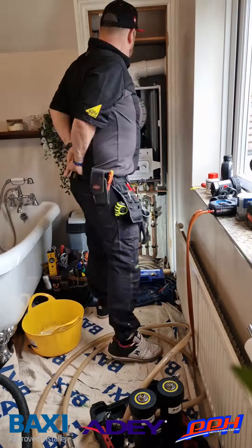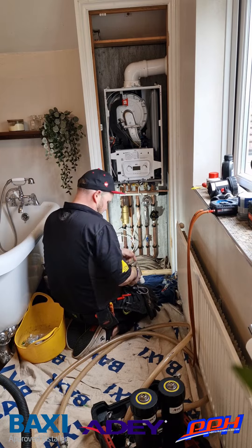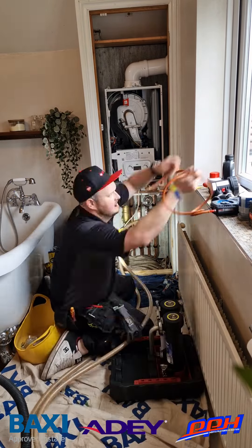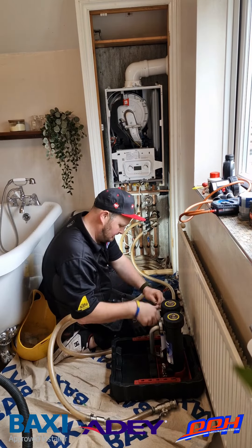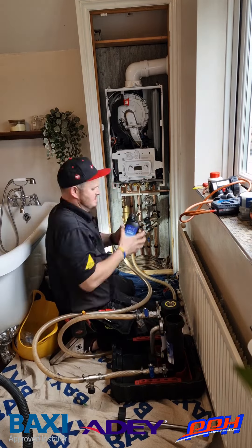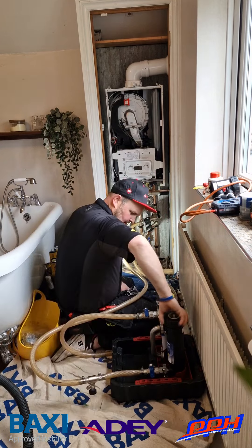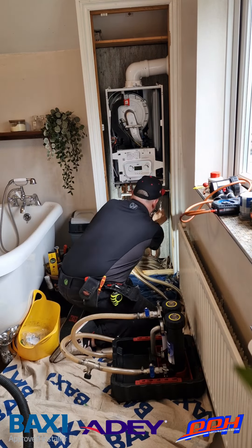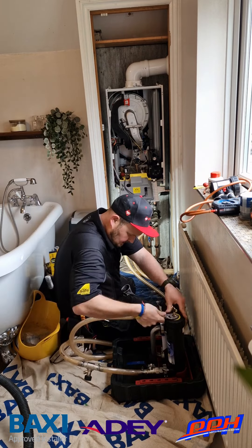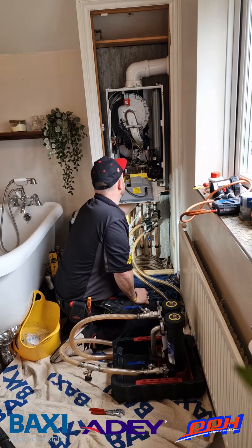Then we're on to the MagnaCleanse — this is the AD system flushing. I use the Cleanse because it goes straight onto the AD valves I've just fitted for the supplied filter. We set this up and add a bottle of MC5 Rapid Flush, which does a great job of cleaning out radiators and pipework in a much shorter time. We then agitate all the radiators and do a cold flush afterwards to make sure we've removed all the cleaning chemical before finishing off with MC1 Plus.